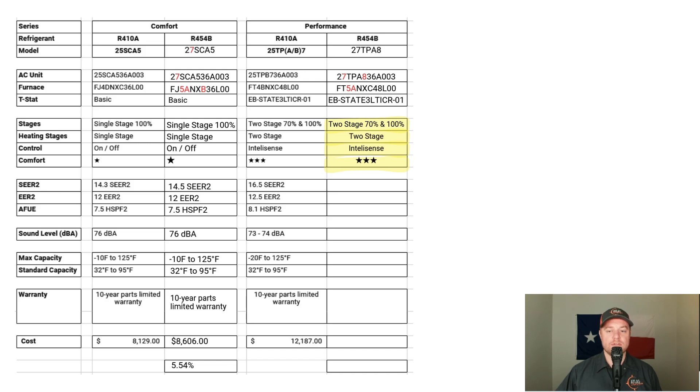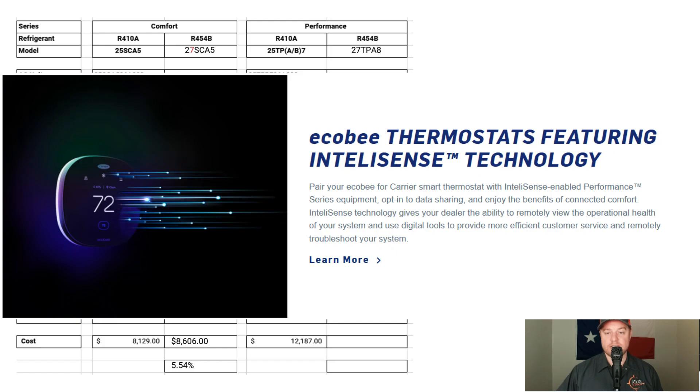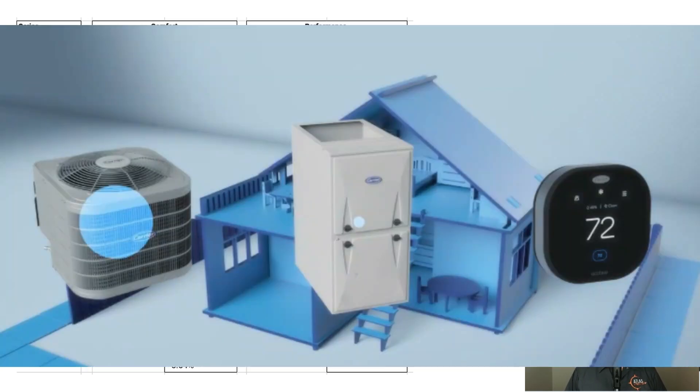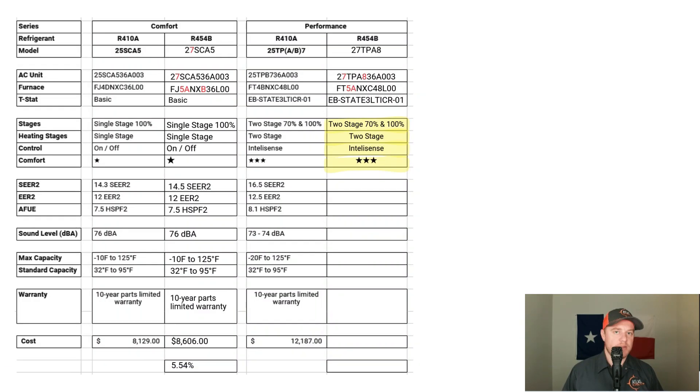What's interesting about the R410A equipment is the model number comes with an A or a B — 25TPA or 25TPB. The A is a standard two-stage system, while the B comes with the ability to use InteliSense. When it comes to the R454B equipment — the 27TPA — it only comes with InteliSense. InteliSense allows lightweight communication among the equipment, primarily to protect it. It can read subcool and superheat values, run error codes if something's wrong, and if connected to the cloud, push those reports to the contractor for faster diagnosis and repair.